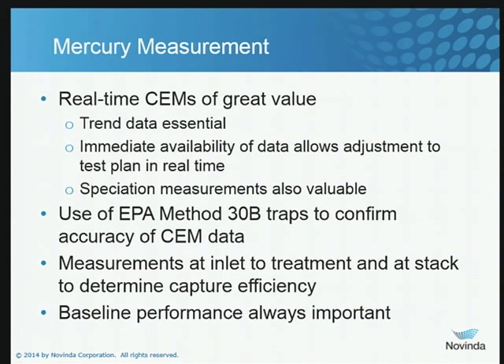I'd also like to see a few Method 30B traps run during a trial so that you can confirm the quality of your CEMs measurements. I like to see some baseline numbers, and we prefer, if at all possible, to be making real-time upstream measurements so we know what the vapor phase mercury content is in the gas stream before it encounters the mercury control technology. Baseline is always important.